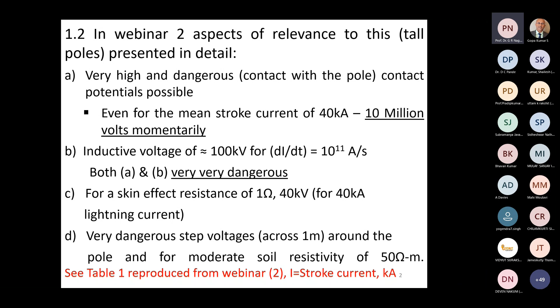And then, once the lightning strikes the tower, the current flows through the ground. I have to mention again emphatically that soil does not have zero resistance. It has a very finite resistivity, typically ranging from 1 to 10 ohm meters for very good soil from our point of view, such as alluvial clay. It's ohm meter, not ohm per meter. A normal soil can be thought of as having anywhere from 40-50 ohm meters to 100 ohm meters. Very rocky or sandy soil can have tens of thousands of ohm meters. We have assumed a value of about 50 ohm meters and calculated the step voltages. That means the voltage across one human step, approximately 1 meter length, and estimated the voltage that can come across one step.